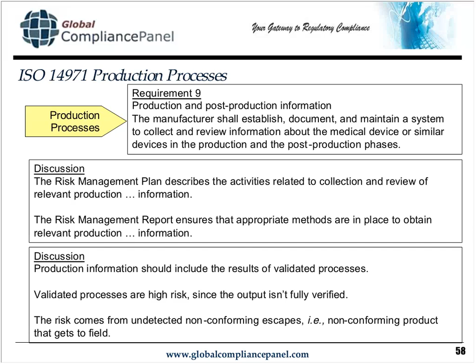The validated processes are often the high-risk processes on the manufacturing floor because they can't be fully verified. In other words, you're shipping stuff that, in theory, nobody's checked. Right? Maybe it's a destructive test, or maybe it's done with a sampling plan. So there are things that are going out the door that have never been verified, and for these characteristics that show up in your risk management plan, it is very, very important that you have a validated process, and so your risk management plan should be collecting that information. You can often get it out of the DHR, the device history record. You're also supposed to be recording the results from the validated process. They go into the device history record. So you're not producing new records, but what you need to be doing is making sure that you're checking them.